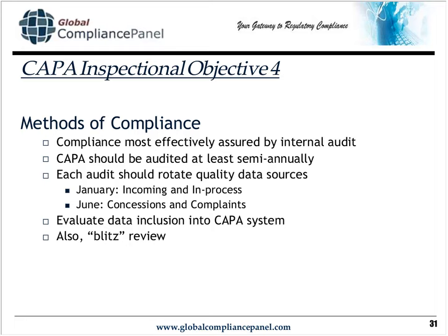I know some firms who do blitz reviews. Let's look at complaints, for example. The blitz review is usually done completely off the books. Whoever's doing the blitz review will take a particular month's worth of complaints, and they'll spend some time and go through the file. They'll look at the forms, the information, the addresses, everything on each complaint. It takes a little while. They'll make sure that all the information is contained there, and then they'll also make sure that the information has been fed into the CAPA system.